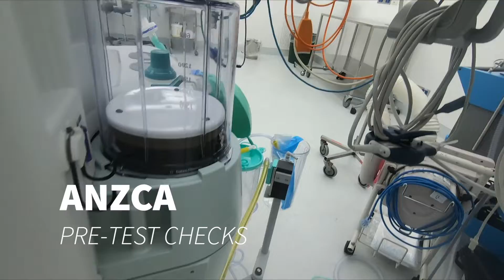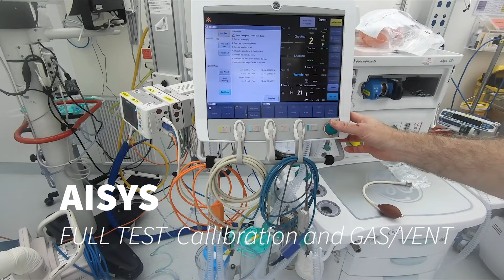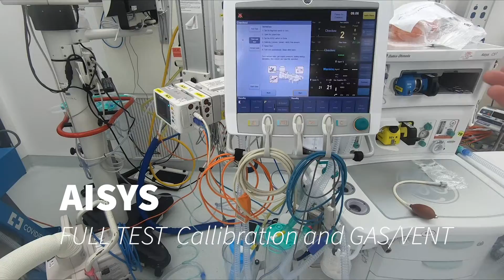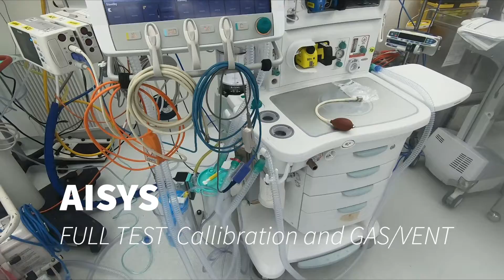Suction runs from the front. Scavenger. You see how it goes to the warm up. Yep, it's all good. Yep, we're going for a full test. Set the bag, then switch to vent. Just hit the back there. The common gas outlet to circle. It's on. Calibrate, remove and reinsert flow sensors. So that's what we're doing there.